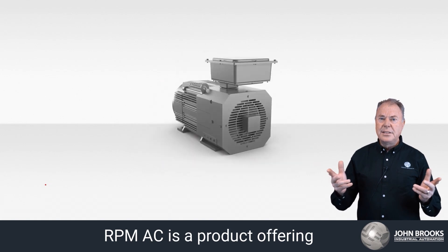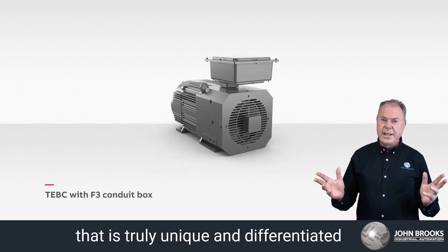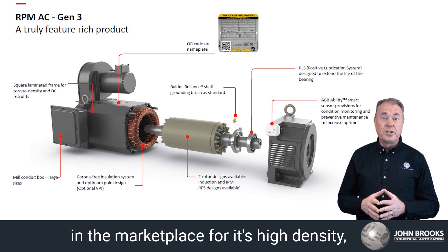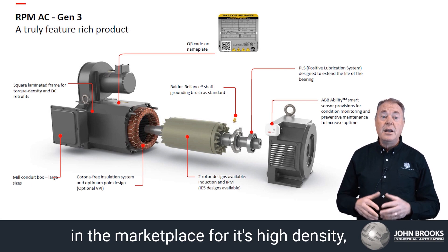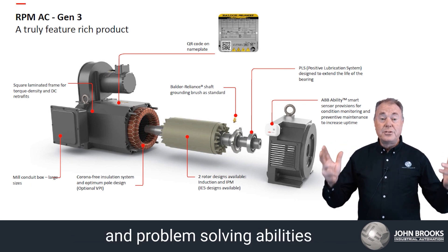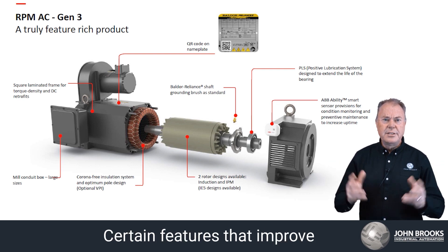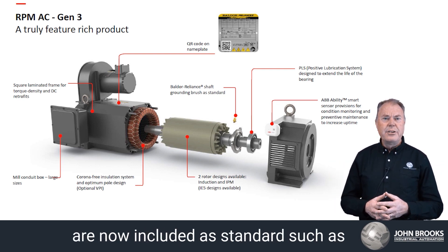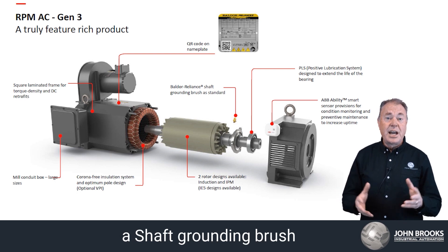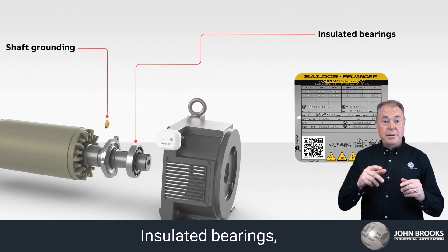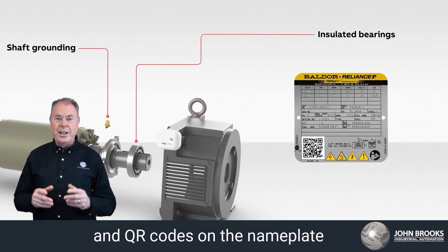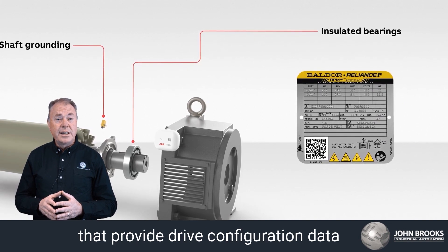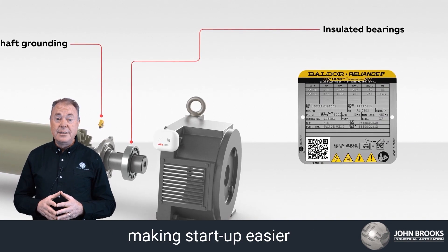RPM AC is a product offering that is truly unique and differentiated in the marketplace for its high density, high performance, and problem solving abilities. Certain features that improve variable speed performance are now included as standard, such as a shaft grounding brush, insulated bearings, and QR codes on the nameplate that provide drive configuration data, making startup easier.